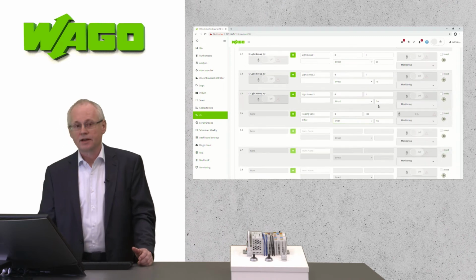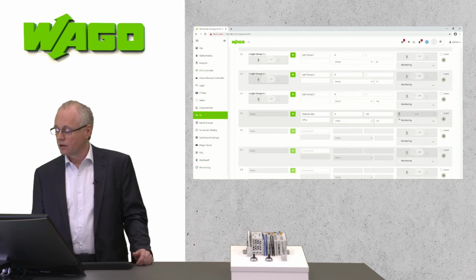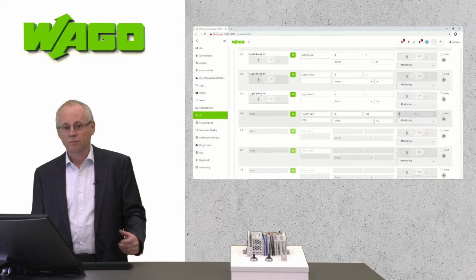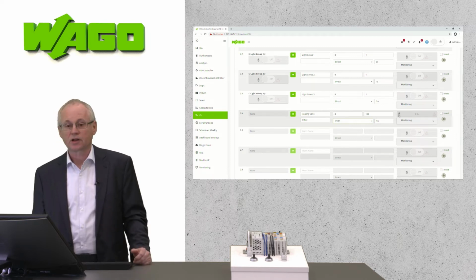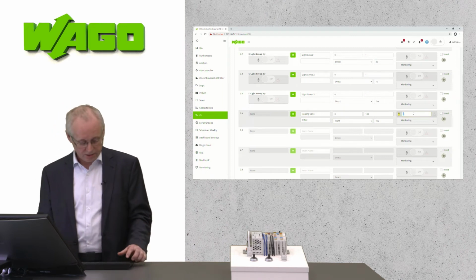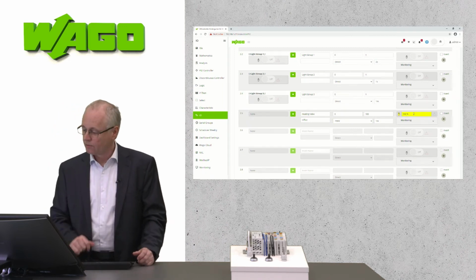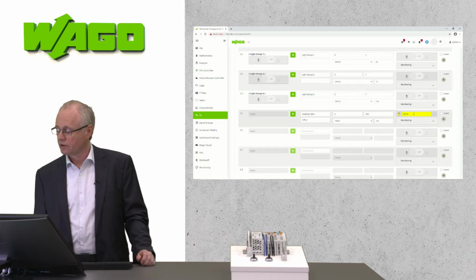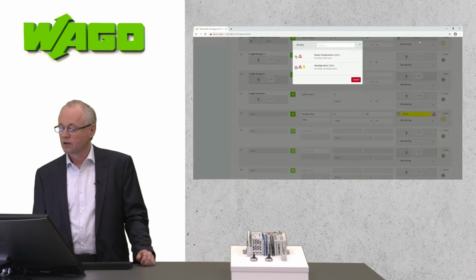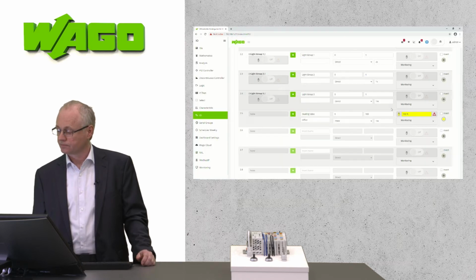Very interesting here is that you can put the data point into a manual override, for example, to check the wiring. Therefore, you can type in here, for example, 100%, and you will see that the output is switched on, and you will also get a message in the upper status bar that this data point is put in manual operation.